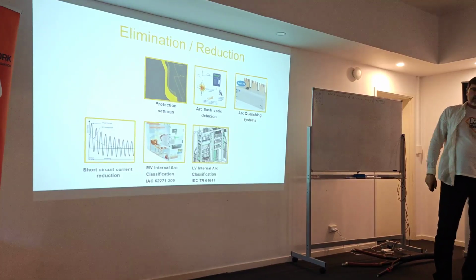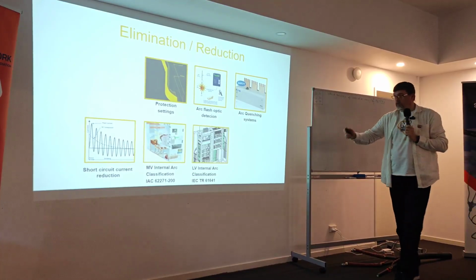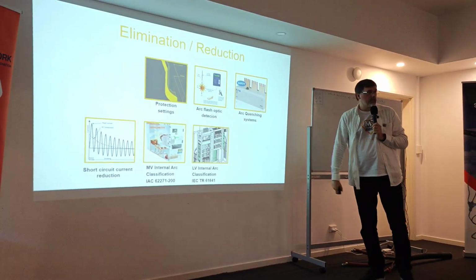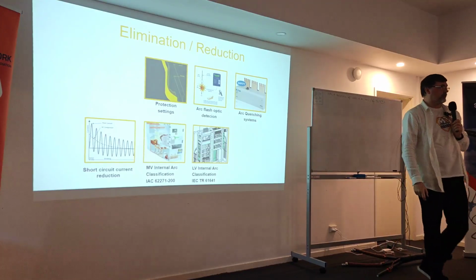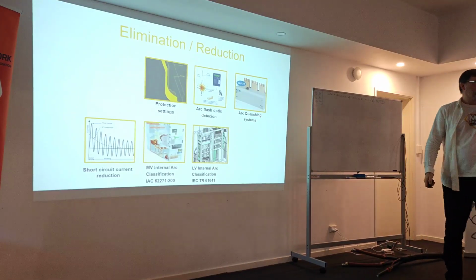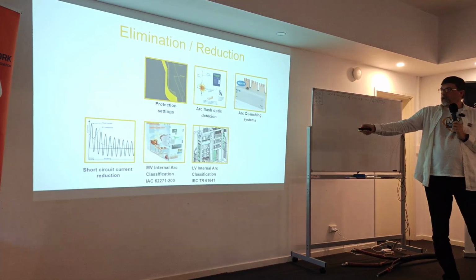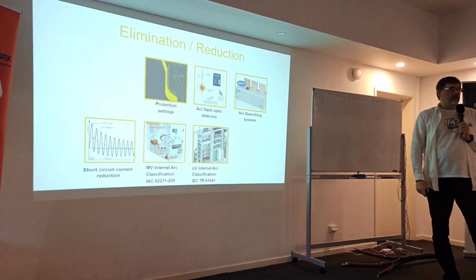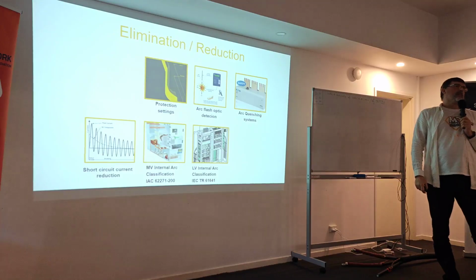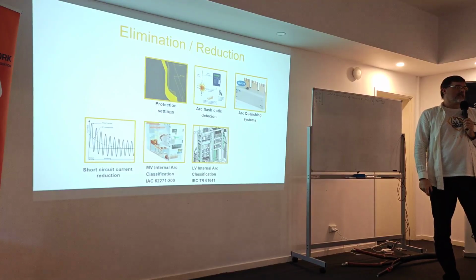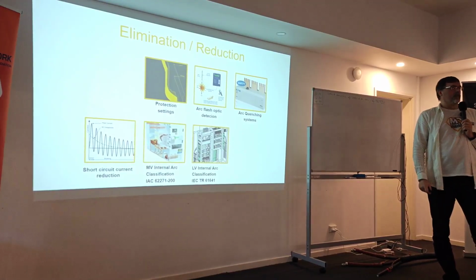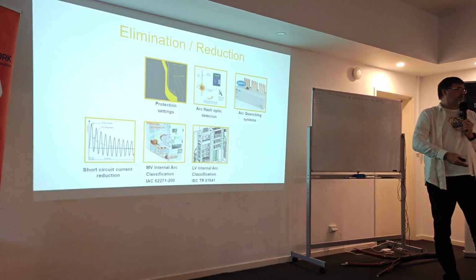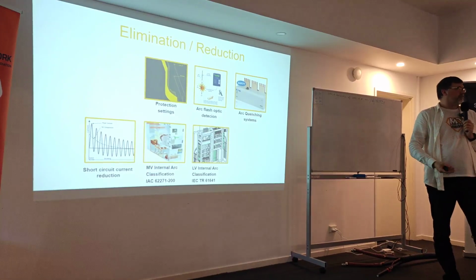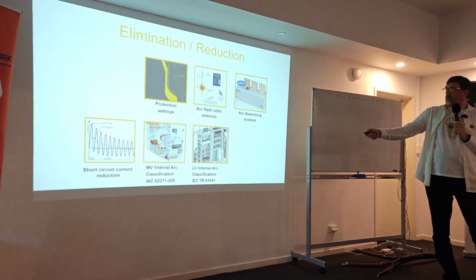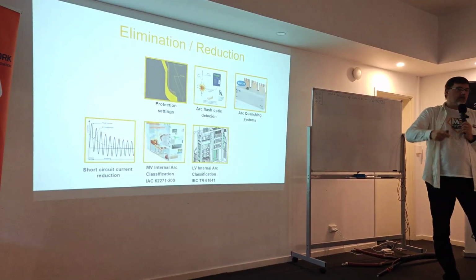So from elimination and reduction, most of the things that we do, what I do typically, we adjust the settings because that's the cheapest thing. Also the hardest to do from an engineering perspective, yeah? But this is the cheapest thing in the field later. However, if you go to the medium voltage relays and changing settings, adjusting and testing and writing the report, it's maybe not that cheap. But if you have people in-house, then technically it's the cheapest thing you can do to improve the safety.